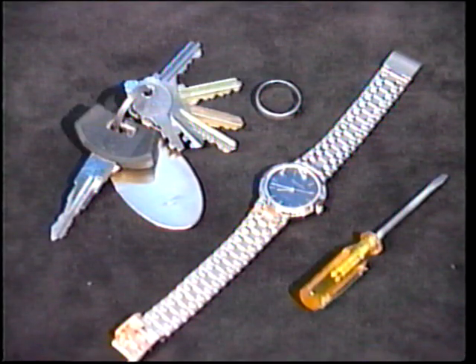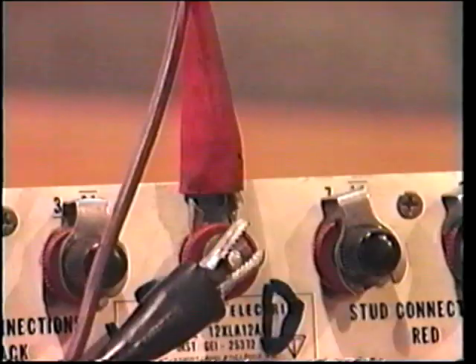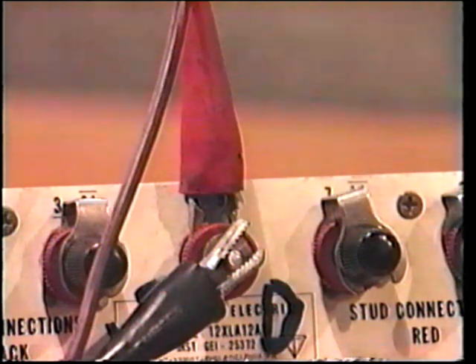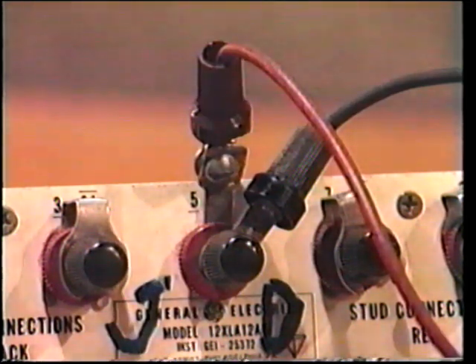This draws our attention to the well-known basic rule that metallic objects, such as rings, keychains, pocket tools, watch bands, and so on, should not be worn when working in the vicinity of live circuits. Also, we should not use jumpers with alligator clips when we are working on current circuits which are in service. A jumper must be used that can be positively secured to a screw connection on a terminal post. In this way, it cannot be accidentally knocked off.